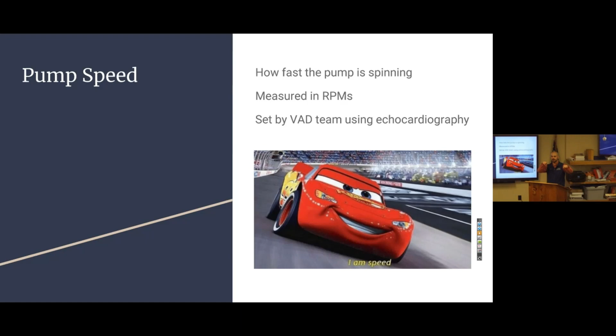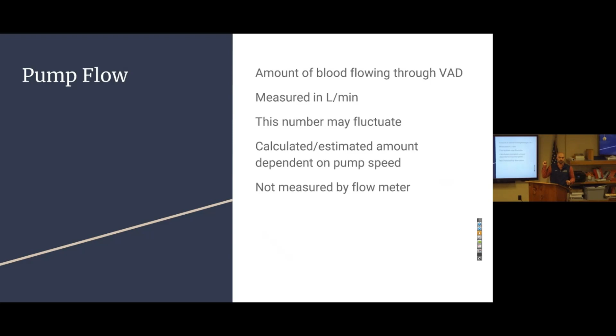Pump flow, this is physically just the amount of blood that is moving through the pump or the VAD. This is measured in liters per minute. Cardiac output is liters per minute. You can essentially use this almost as like a surrogate for cardiac output, right? Normal cardiac output is 3 to 5 liters a minute. If you have an endurance athlete who's running the Olympics, they can actually get up to like 35 liters a minute. They're crazy. So you usually start seeing problems when it drops below that 2.5 liters a minute. So think of this almost like cardiac output. This number can fluctuate, okay? Caveat, on most of these devices, this is actually a calculated number that's getting presented to you on the device. It's not actually measured by a flow meter, okay? So there can be some discrepancy, but if you're looking at your patient and they look like they're not perfusing well, and it's telling you that they have good flow, remember this is a calculated number, okay?